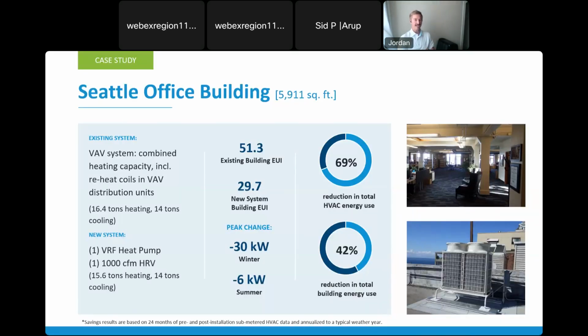So this is a Seattle office building, or rather one floor of a 5-story building. This is a tenant improvement that had an existing VAV with electric reheat. It's around a 15-16 ton building or HVAC system. Pre-conversion EUI was 51 kBTUs per square foot per year. New building EUI was 29. So we had a 69% reduction in HVAC energy, right on average with other buildings in the region, and a 42% reduction in building energy.